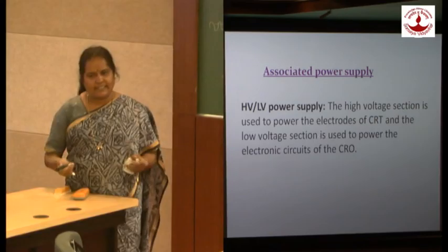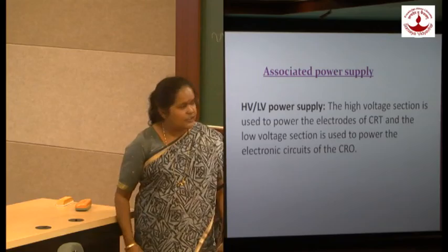The seventh system is the power supply, which is of two types: high voltage and low voltage. The high voltage — around 1,500 to 2,000 volts — is applied to the CRT to accelerate the electron beam to very high velocity. The low voltage is for all the associated circuits required for the functioning of the CRO. This is how the CRO works, giving a visual display of the waveform under test.